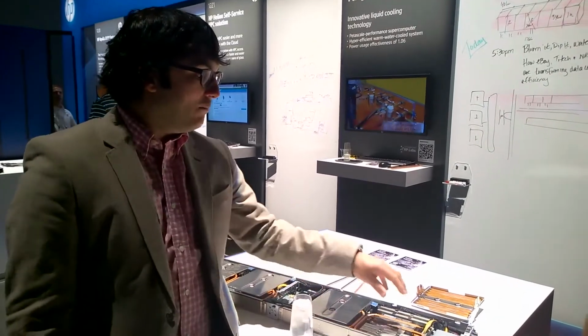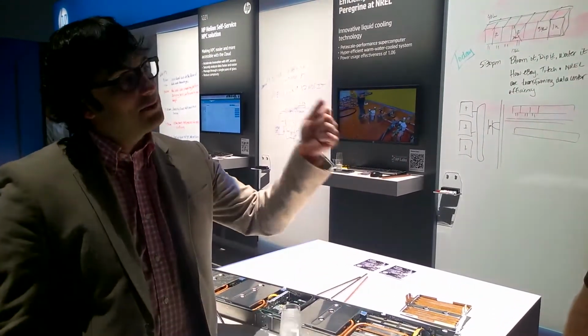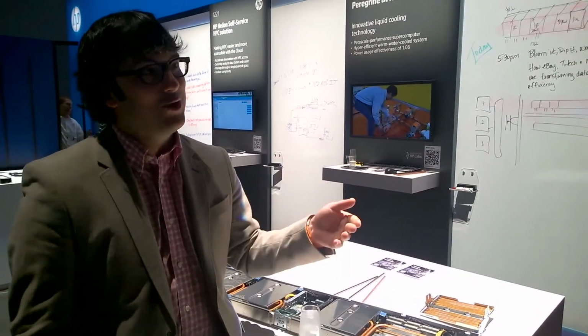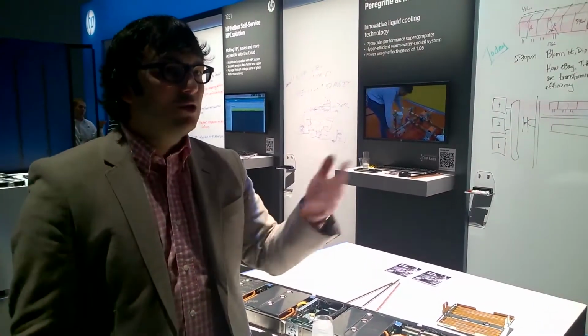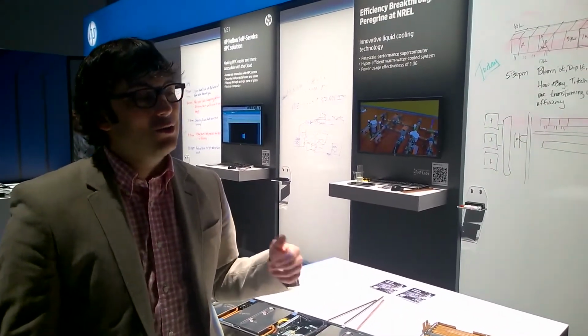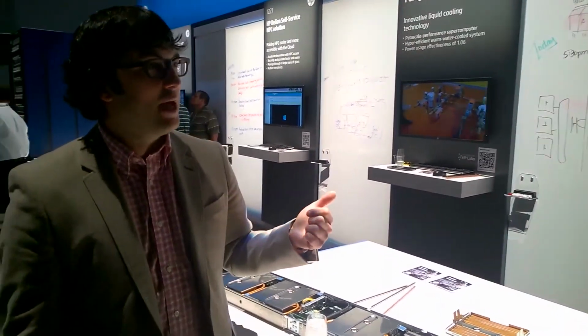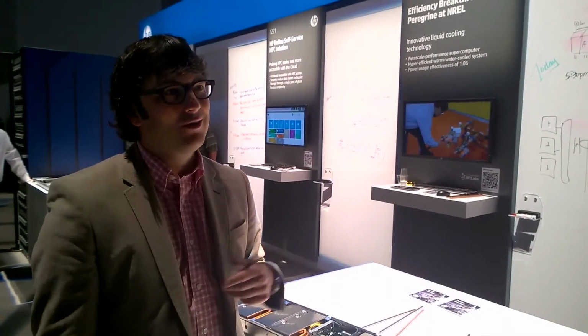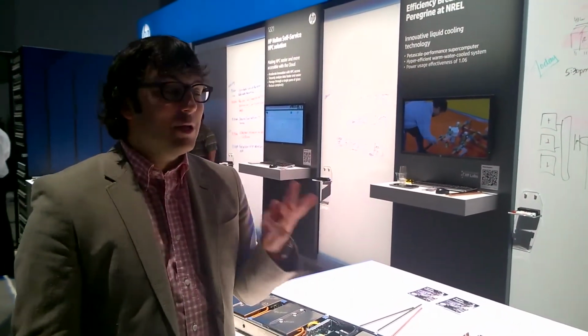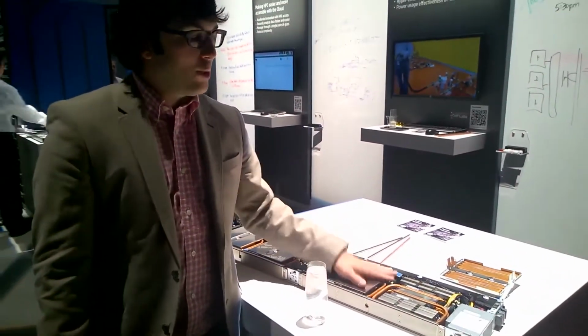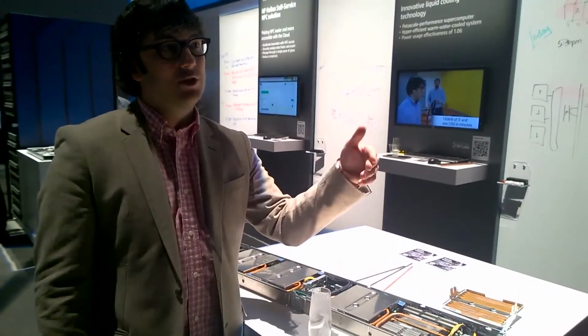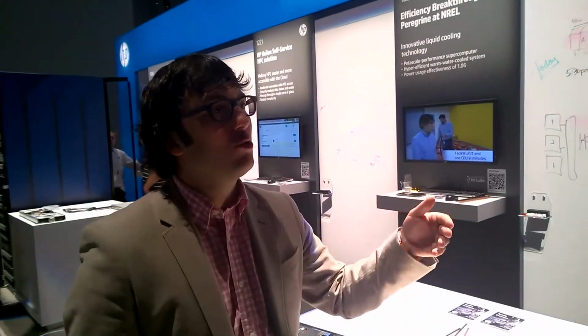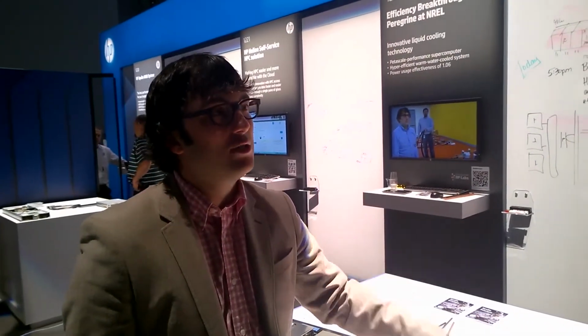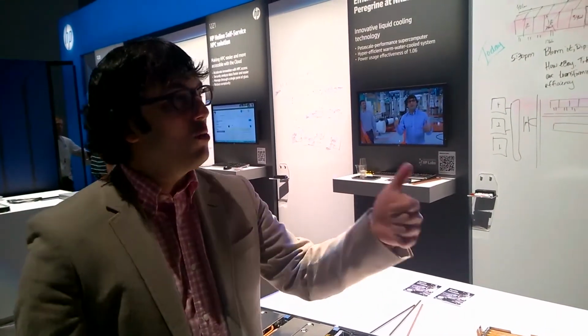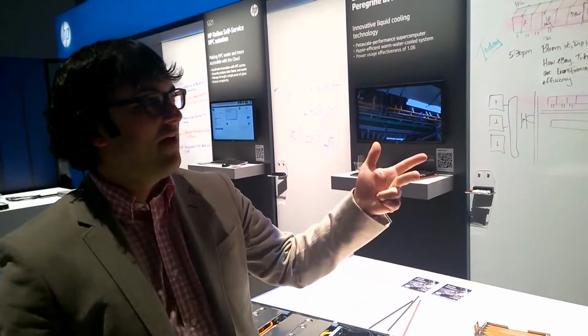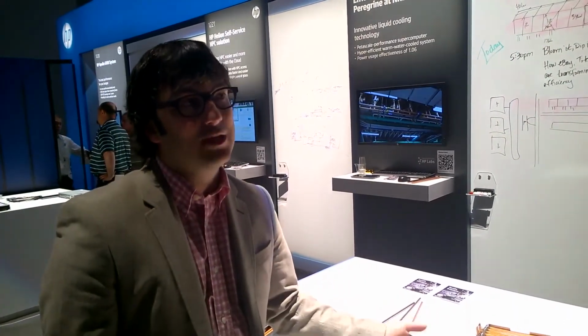Advantage number two is that because you're running the system with warm water, hot water comes out of it, and then you can do heat reuse. NREL is using their 12-rack system as a furnace in the wintertime. They're heating their 10,000 square foot office space and 40,000 square foot of labs with the computer, and they don't need any other furnace. That's outstanding too. Last but not least is better component thermals. A liquid cooled server will allow you to support the top bins for CPUs, think north of 125 watts, so 135 watt, 145 watt CPUs, and keep the thermals more constant. No more hot spots, no more air starving for servers, no more fans running like crazy. Liquid cooling really brings you more performance at the silicon level as well.